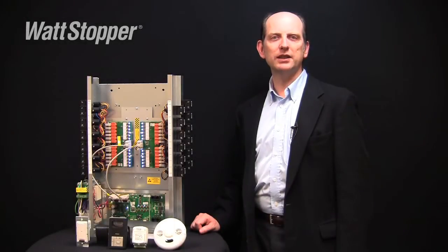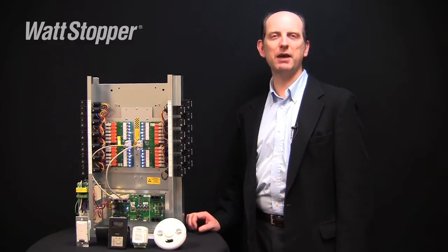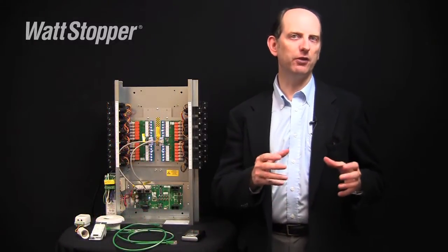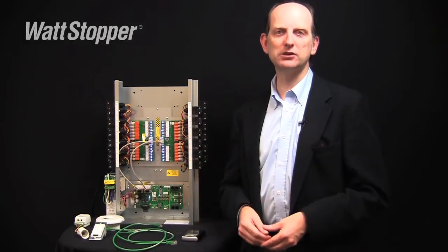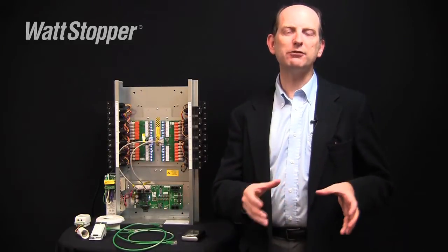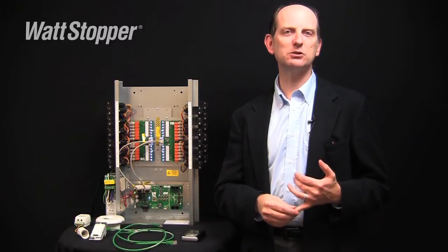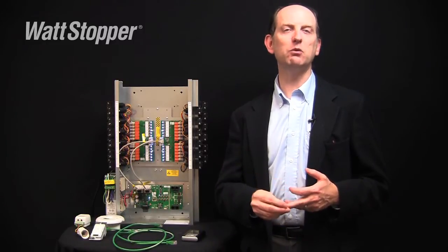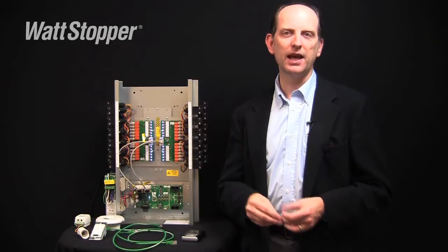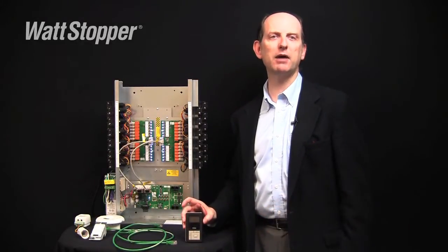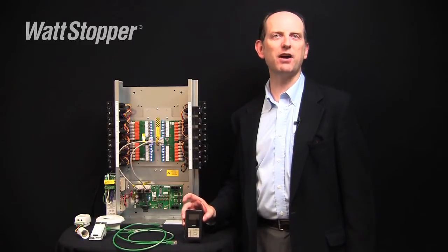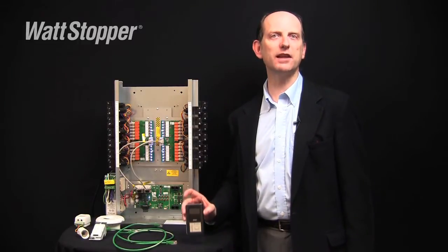In this video, we'll continue to walk through the process of configuring a digital lighting management relay panel and accessories. Just like other DLM components, there are different settings you can have for the normal hours and the after hours time period. For normal hours and after hours, you can change how occupancy sensors work, the time delays, blink warnings, and other settings. As discussed in the first video, setting these behaviors for relays in the panel is done by creating groups of relays and specifying the parameters all at once using the LMCP.